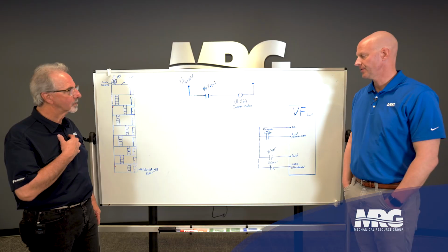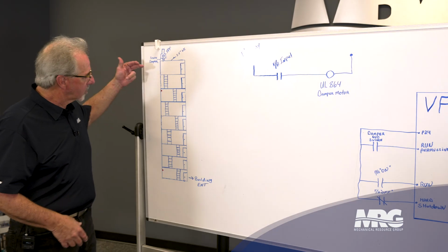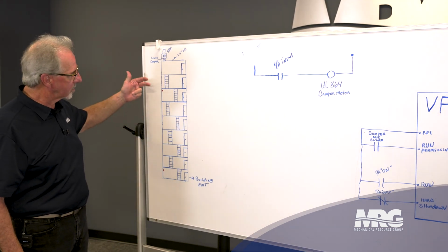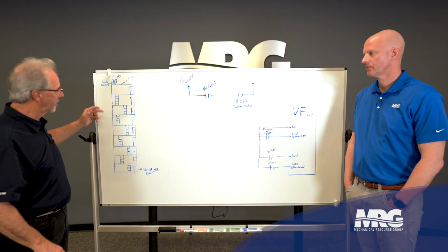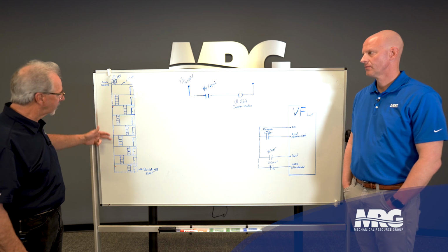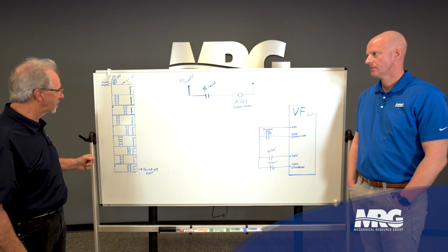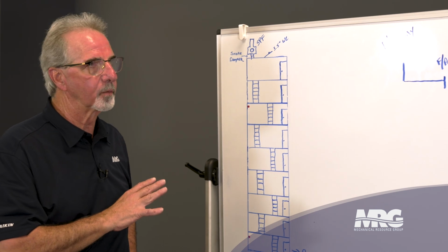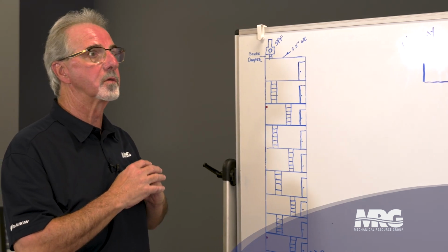Show me what we got going on here in this diagram. I wanted to show you a representation of a 9-floor building. And basically what this is, is a stairwell. Excuse my artistry, I'm not the best in the world, but this will give us an idea of what the function is. Now, in the old days, back when we used to do stairwell pressurization, it was just based on a single speed. TAB would come in and they would say, hey, run that fan at 45 hertz.